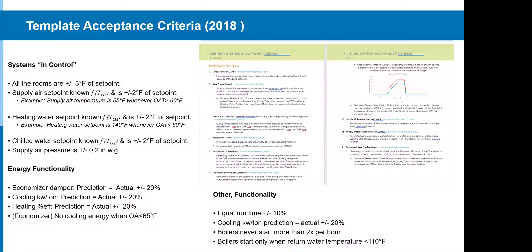Starting in 2020, our commissioning standard implemented connected commissioning, and basically controls design responsibility for the commissioning agent. We got sick of hearing that we'd have an engineer of record who did the controls design, the commissioning agent would issue comments and critiques on the controls design, and those comments wouldn't get picked up.